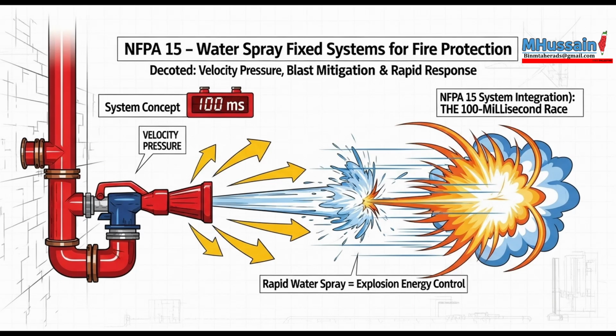And the pressures required for UHS systems also reflect this need for speed. They do. The minimum operating pressure at the most remote nozzle is significantly higher than standard systems. At least 50 psi, that's 3.4 bar, section 12.3.3.1. You need that high pressure for rapid water acceleration and also to guarantee the spray pattern forms perfectly, instantly for immediate cooling or dispersion. And the density is higher too. It's much higher. Minimum design density for area application is 0.50 GPM/ft² according to 12.3.2.3. That's double the standard rate we discussed for just structural exposure protection. You need a lot of water very fast.